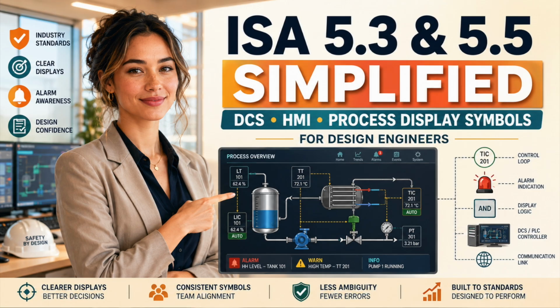Look at the displays in your own project and ask yourself 3 uncomfortable questions. Can an operator distinguish command from actual state? Can an operator recognize invalid data before acting on it? Can an operator understand what remains available after the primary control path fails? If the answer is unclear, the graphic is not finished.